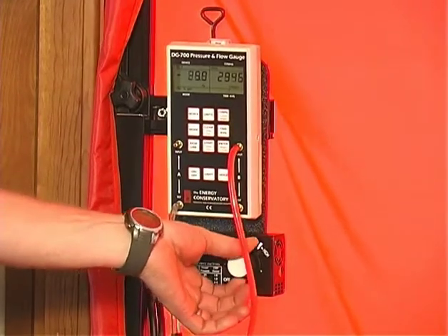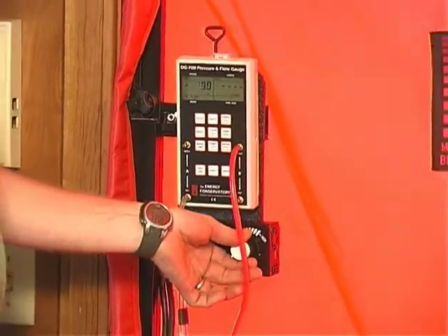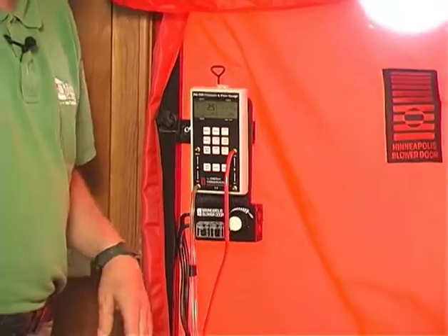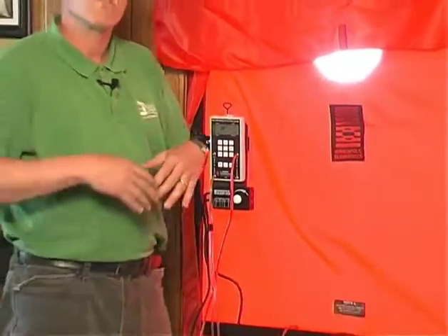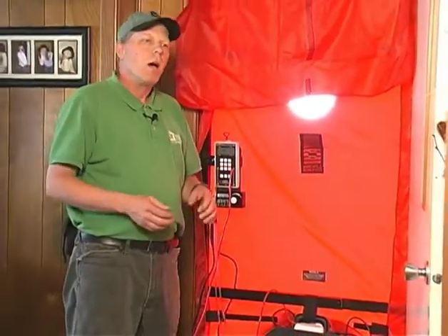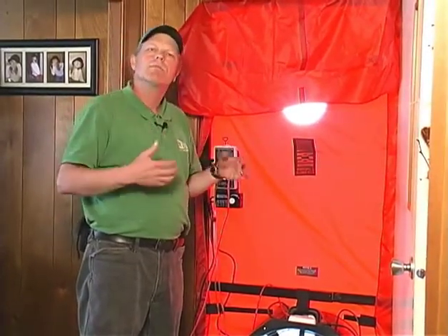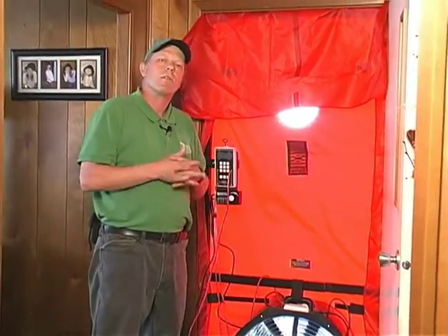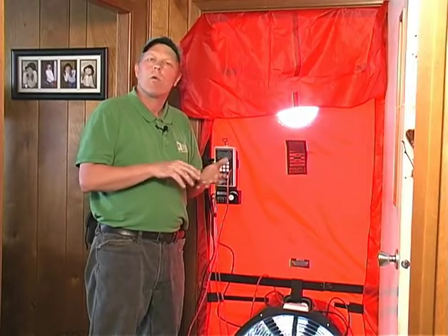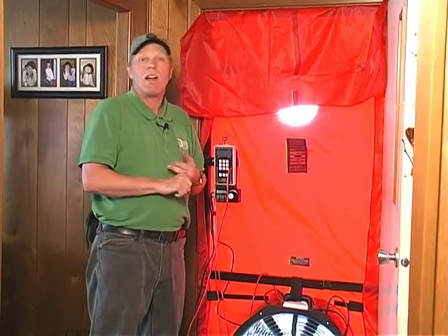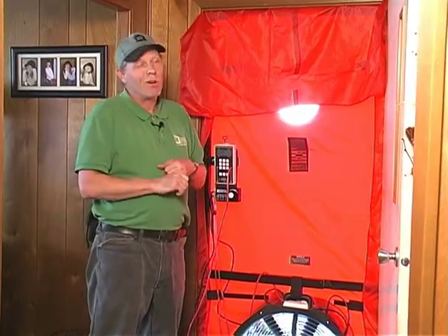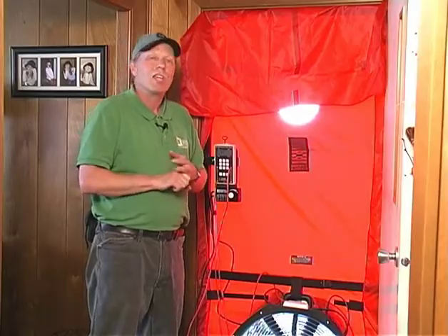which, the approximate leakage area of a home at 3,000 CFM50 is 300 square inches of leakage across the building envelope. This is a double wide mobile home. It's not very large, but that would be considered on the leaky side for either a single wide or a double wide. A double wide is twice as big as a single wide, so it's still leaky.